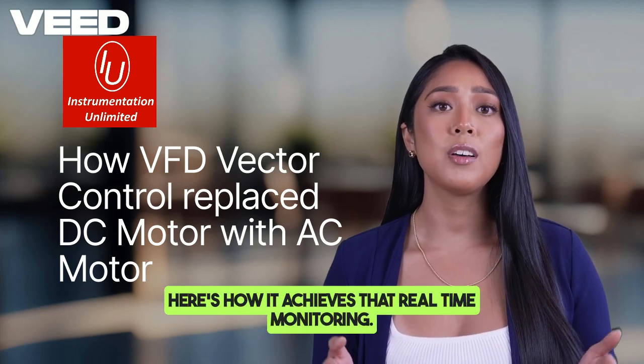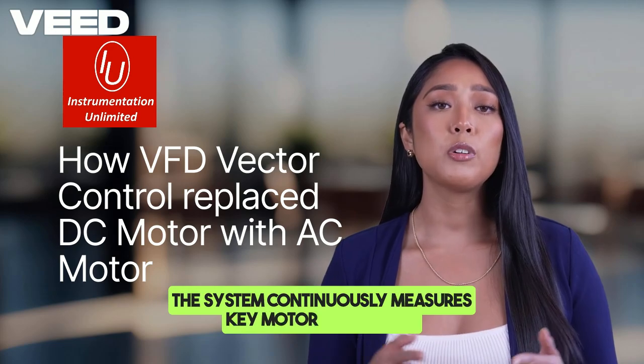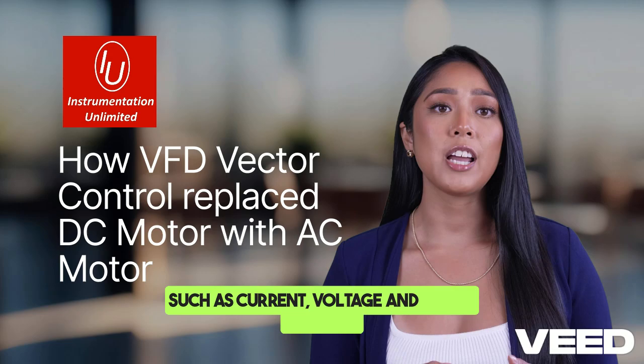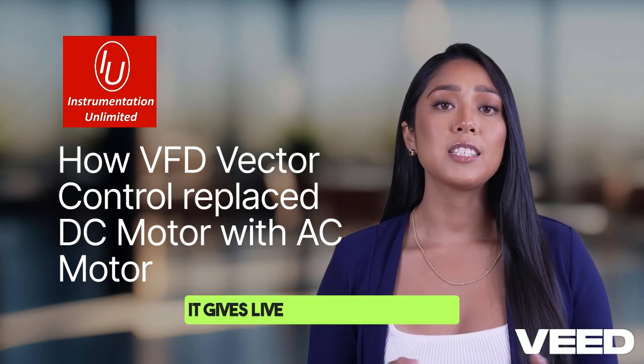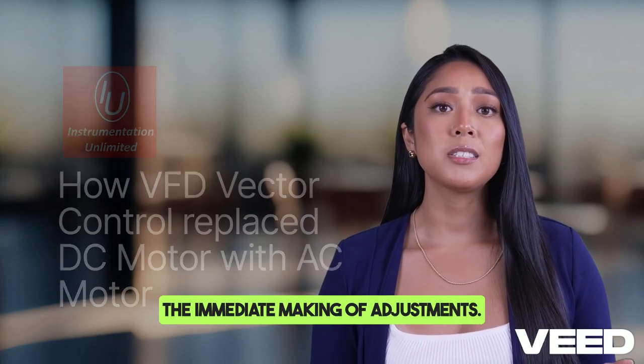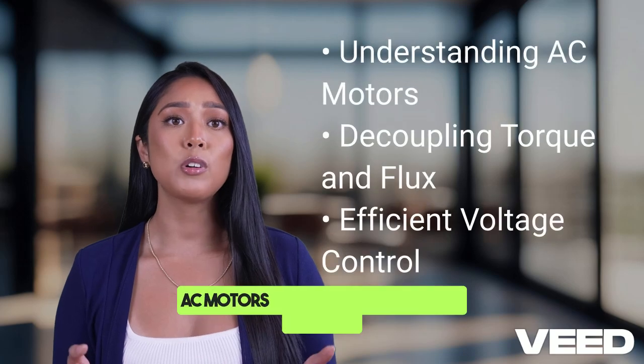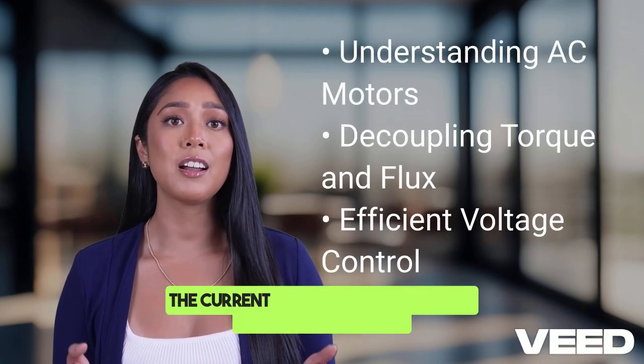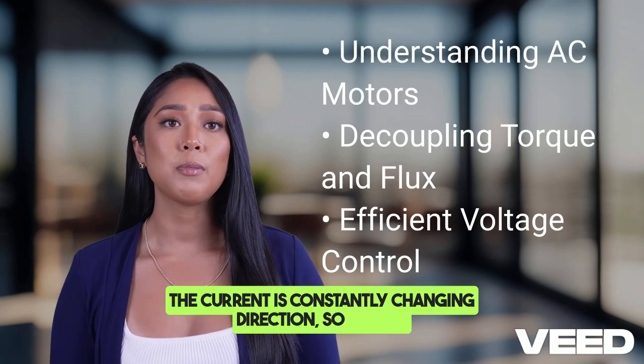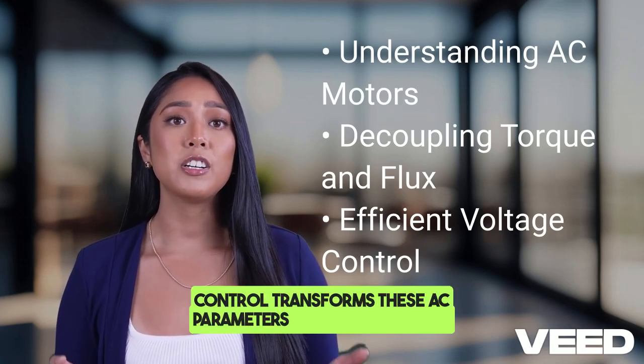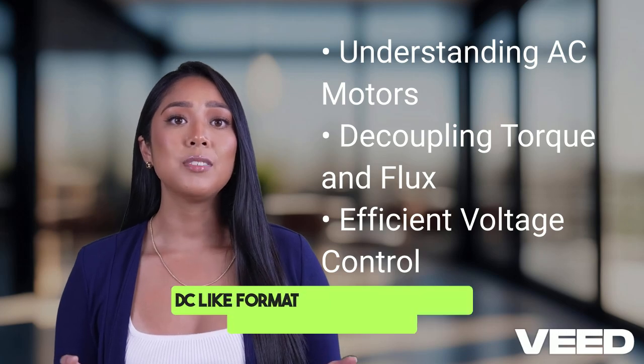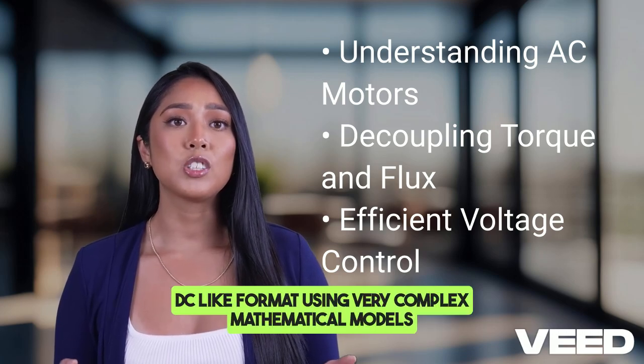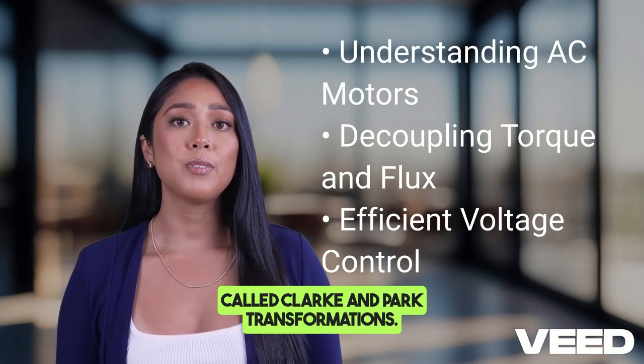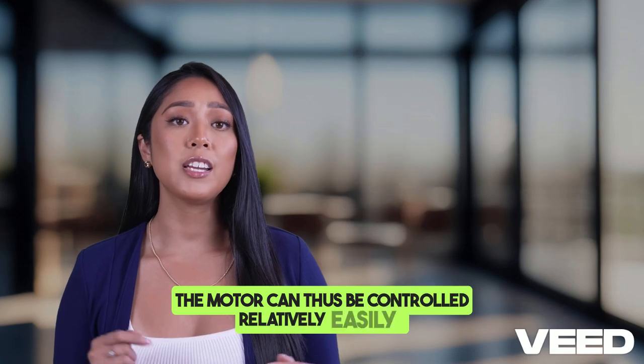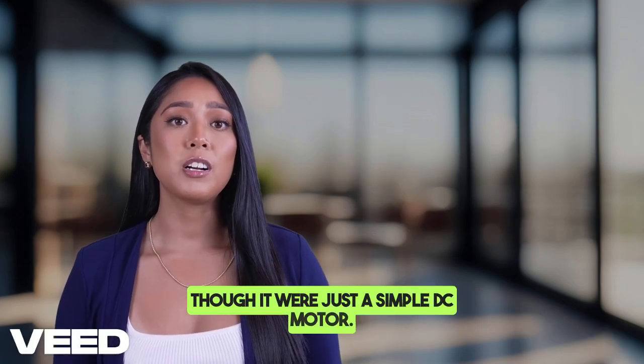Real-time monitoring. The system continuously measures key motor parameters, such as current, voltage, and rotor position. It gives live feedback, allowing the immediate making of adjustments. Mathematical transformation. AC motors work off alternating current. The current is constantly changing direction, so vector control transforms these AC parameters into an equivalent DC-like format using very complex mathematical models called Clark and Park transformations. The motor can thus be controlled relatively easily as though it were just a simple DC motor.